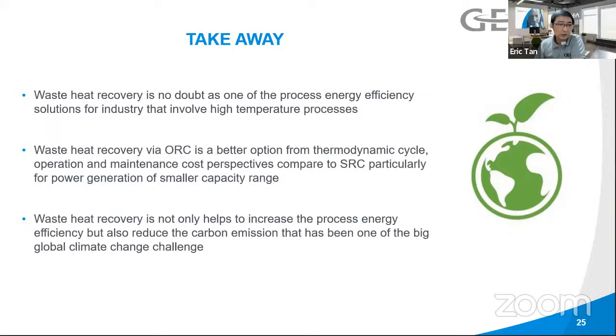Second, waste heat recovery with this ORC is a better option from a thermodynamic cycle and operation and maintenance cost perspective compared to the steam cycle, particularly for power generation in a smaller capacity range, I would say anything below 10 megawatts.